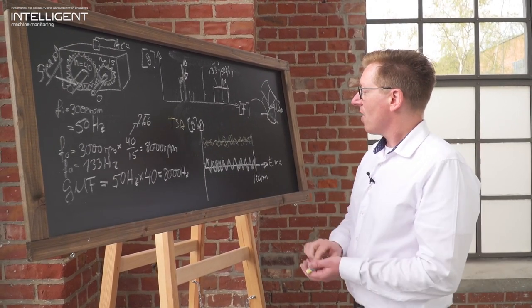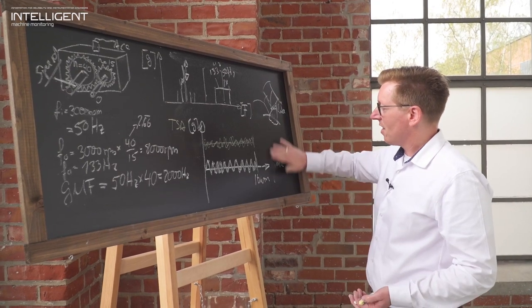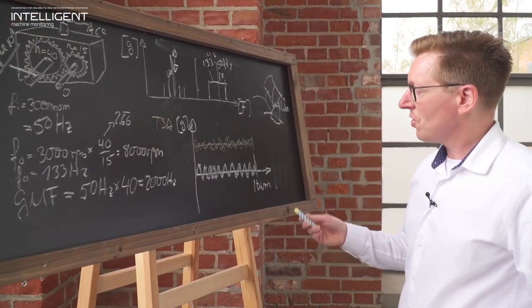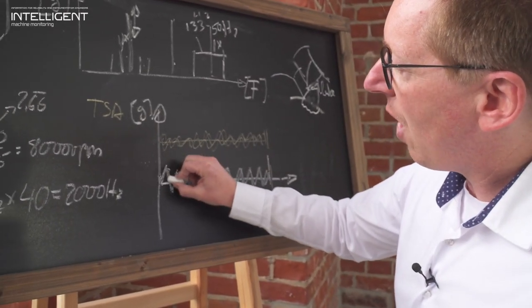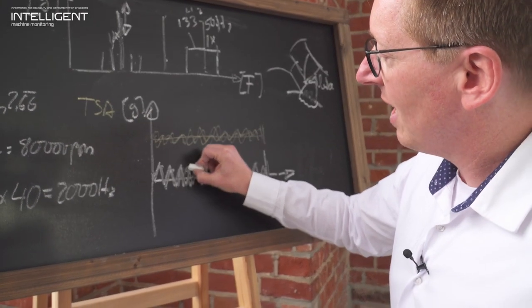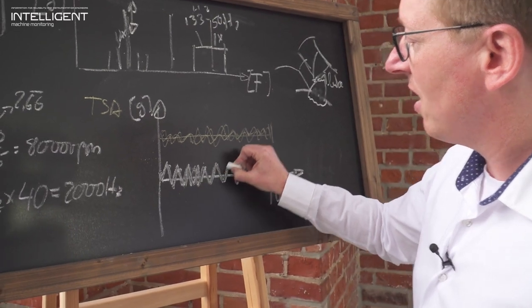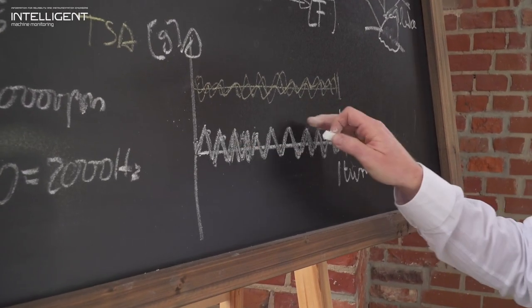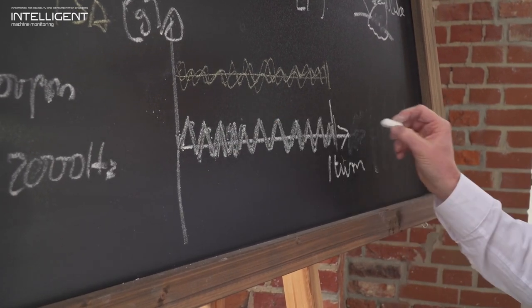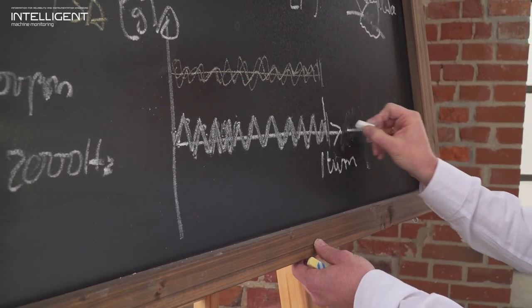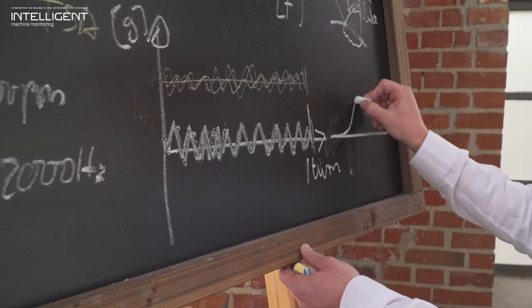This TSA is then further analyzed in a so-called kurtosis analysis. The kurtosis is a reflection of how even, how equal each contact is compared to the one next to it.